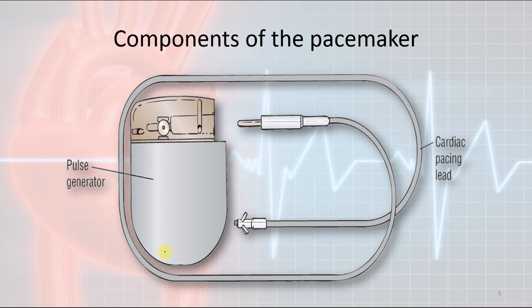As you can see here, this would be your housing for the pacemaker that would have the battery and all of the electronics, the transmitters, the receivers, the circuitry necessary to run the pacemaker. And then the pacemaker wire would fit into this spot right here. What I like about this picture is that I want you to take a look at the tip of this pacing lead right here. It looks like it's a wire that has some barbs in it. The function of those barbs is to stick into the right ventricle wall, into that endocardium and part of the myocardium there, to really hang on during the forceful rigors of contraction.